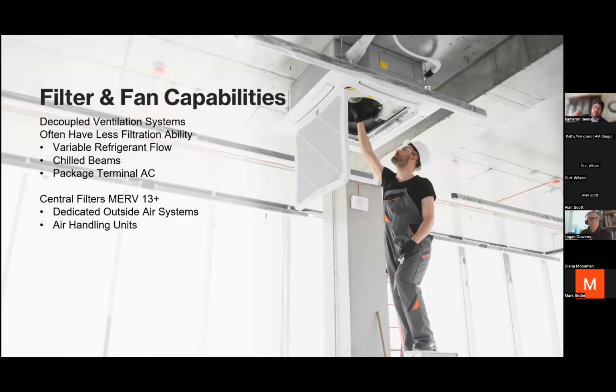There's one note though, when we look at these decoupled systems, the terminal unit or the heating and cooling unit that's actually in the zone in the space, providing the heating and the cooling, like with a variable refrigerant flow system, those are often hard to get a MERV 13 or better filter on without special consideration. And then chilled beams, of course, don't have filtration on them. And so those could just be simply recirculating the air. Now, I'm not saying don't use these systems because these systems are very much a good thing from an energy perspective, but just work very closely with your mechanical engineer, especially if you are in a wildfire smoke prone area.